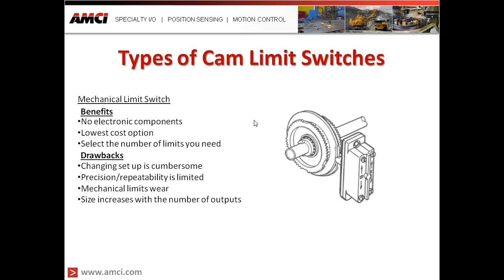Some drawbacks of a mechanical limit switch are that changing the setup is very cumbersome — you often have to get in there with a tool, typically a wrench, to adjust them. The adjustment is very coarse and getting back to the same position between setups is very difficult, often impossible. Mechanical limit switches wear, so replacement components are needed. As the number of outputs increases, so does the size of the unit, requiring much more space for mounting.